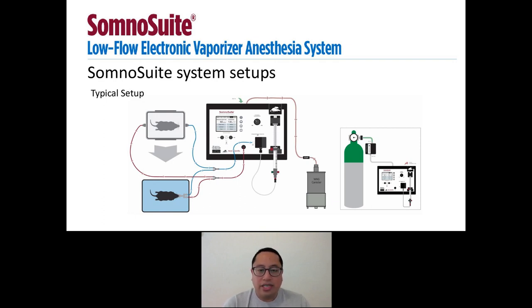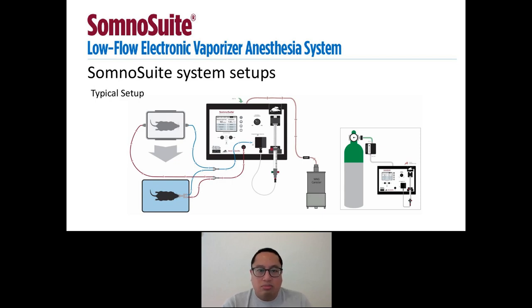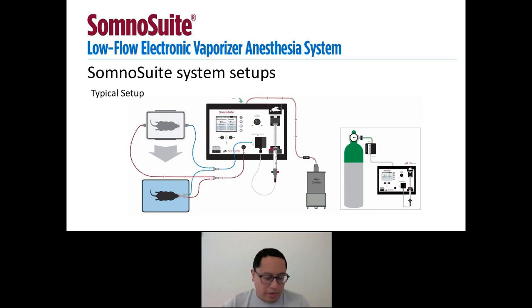If you choose to connect your SomnoSuite to compressed gas, the incoming pressure from the compressed gas tank must not be higher than 15 psi in order for the SomnoSuite to work properly. In a smaller diagram to the right, a preset pressure reducer is connected between the compressed gas tank and the SomnoSuite to bring the pressure down to 15 psi. If you do choose to use compressed gas, we are more than happy to discuss your setup with you.